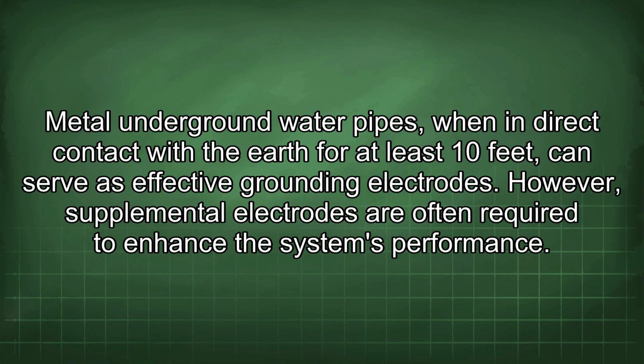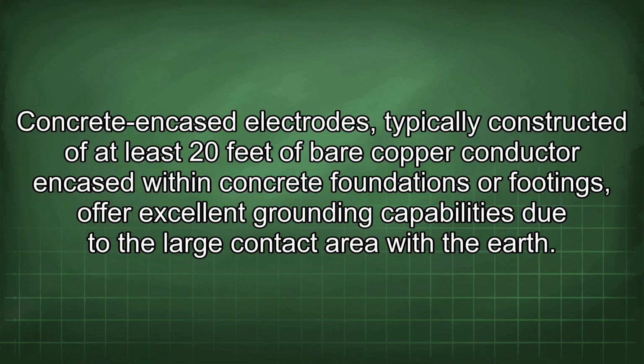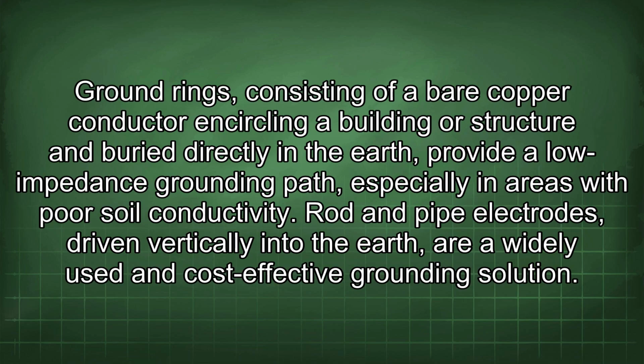Metal underground water pipes, when in direct contact with the earth for at least 10 feet, can serve as effective grounding electrodes. However, supplemental electrodes are often required to enhance the system's performance. Concrete encased electrodes, typically constructed of at least 20 feet of bare copper conductor encased within concrete foundations or footings, offer excellent grounding capabilities due to the large contact area with the earth. Ground rings, consisting of a bare copper conductor encircling a building or structure and buried directly in the earth, provide a low impedance grounding path, especially in areas with poor soil conductivity.